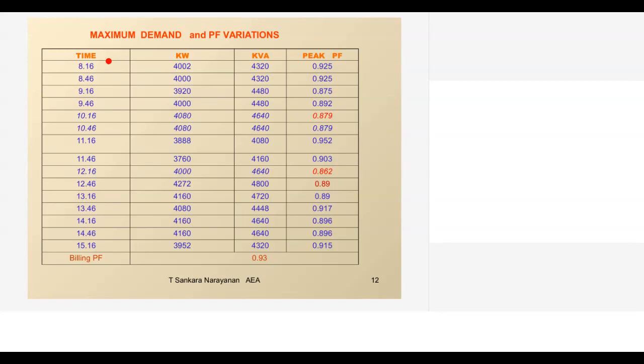This is again an engineering industry, but the only advantage is that this engineering industry is almost running like a process plant. All three shifts are making production. There is no change in second shift, third shift load. So for this, again through the billing meter, for a half hour cycle we can monitor how the kilowatt and kVA are varying. Here, if we see the PF at peak time, when the load is higher, it is going to 0.86 or 0.87, whereas this industry had an average billing power factor of 0.93. That means if you go by the bill data, everything looks good. If we monitor exactly for the loading cycle, then we will know what the additional compensation is.